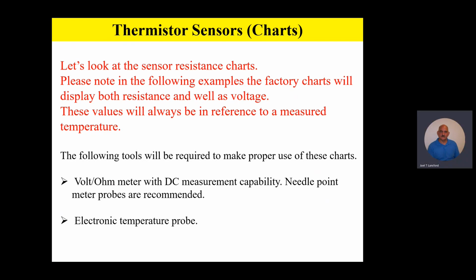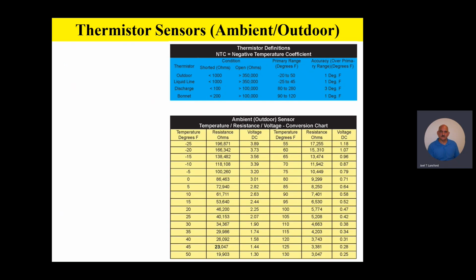So let's take a look at those charts at this time. So we'll notice on this particular chart, we're looking at the ambient or the outdoor temperature sensor chart. And let's do a couple examples together. So let's say, for instance, we go to the chart and we measure our outdoor temperature, and let's say our outdoor temperature in this example is 10 degrees outdoor air temperature. Now, if you take a look at the chart very closely, you're going to notice that 10-degree temperature on the left-hand side of the chart. If we remove that sensor from the board, you'll notice that in the resistance or the ohms column on the chart, it'll tell you what the ohms or the resistance of that sensor should be at 10 degrees outdoor air temperature on the ambient sensor.